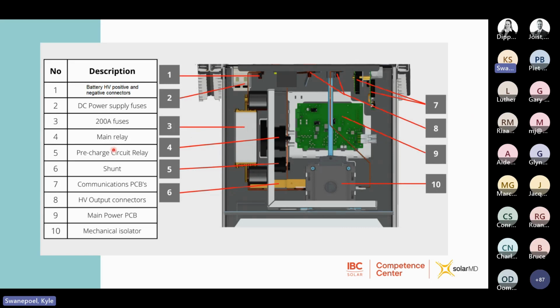Then you've got the main relay over here. This relay is your software disconnect from the battery. If all conditions are met and it's in a happy state, the relay will be in the closed state and power will be allowed to flow. But if there is an event where it's overcharged or under discharged, this relay will disconnect the circuit and the output from the battery will stop.